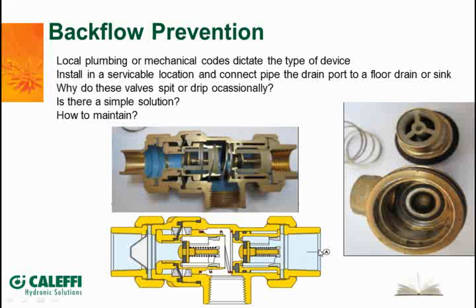And that's the seal that's keeping anything that's going to backflow from here, or even from this side, from dripping out of your drain. So if this seal right here becomes compromised, then you've got the potential for this thing to drip out from either side. So this seal is very critical and important. And 99% of the time when we get one of these back, there's going to be something lodged in this little seal surface. It's going to be a piece of Teflon tape, or a copper chip or something like that that's come through the water system and gotten in here.